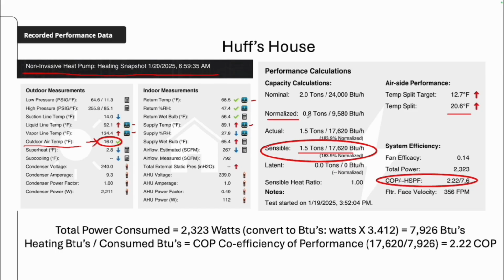Now, just to make sure, because I know people will question this, if you see this normalized here in Measure Quick and it says 0.8 tons at 9,580, that is based on just a generic 14 SEER heat pump. And so this is why we want to make sure we measure against the actual and compare against the actual OEM's data and not use normalized in the heat mode. Now, in the cooling, when you're setting up your cooling profile in Measure Quick, you can put the extended performance tables into Measure Quick on the cooling side, but not the heating, because it just varies so much.